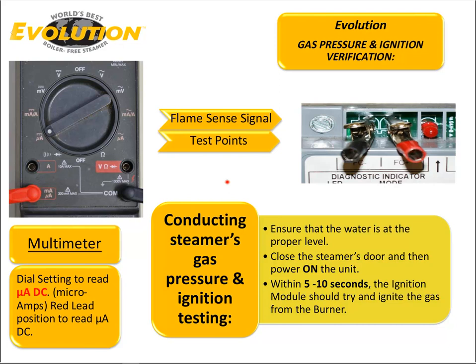It's either too low on the burner or too high, and that would then feed back into your gas pressure. You'll want to check that you are at 5 inches water column. You may need to adjust to bring the flame into contact with the flame sensor.